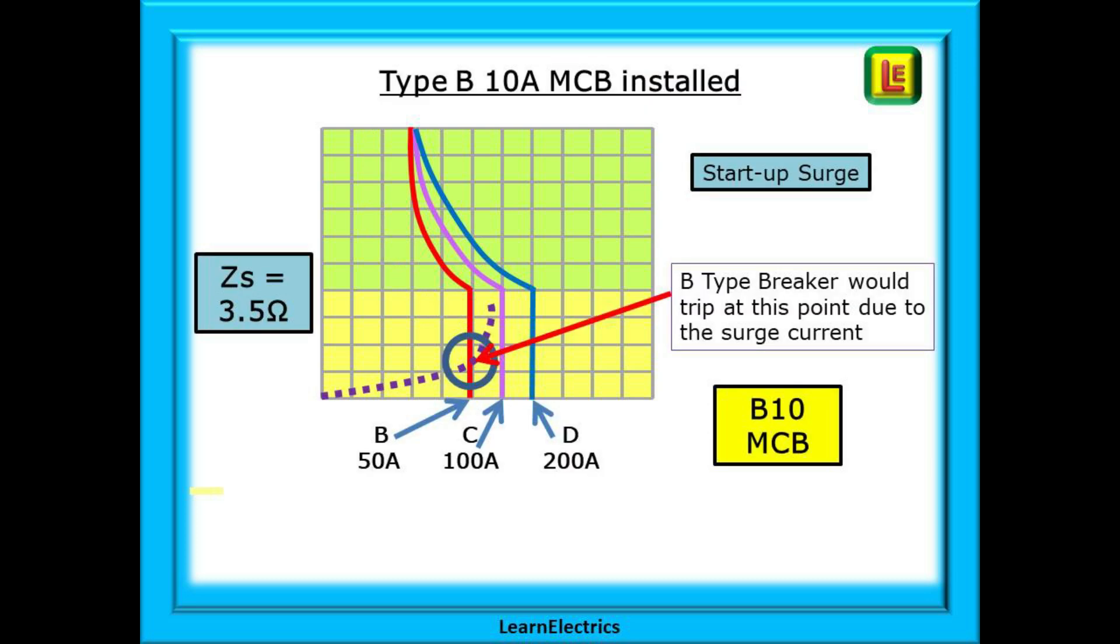What would happen though if this was a small workshop with instead a lathe with an electric motor? It is still a type B 10 amp MCB and the ZS is still 3.5 ohms. The startup surge of the motor is much greater due to the nature of electric motors. The purple current line in our example surges past the B type red line. The MCB trips, cutting off the power to the lathe motor at the point where the red line is crossed.